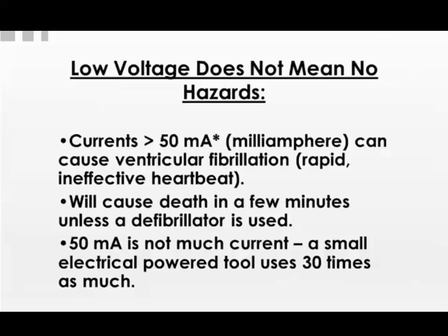Now, one misconception that I hope after this presentation will help mitigate is our misunderstanding that low voltage means no hazards. Now, the lower the voltage, the less opportunity an arc flash occurs, but low voltage can still cause catastrophic events. So currents greater than 50 milliamps, or milliamperes, and that's not a lot of power, can cause ventricular fibrillation. That's that rapid, ineffective heartbeat.